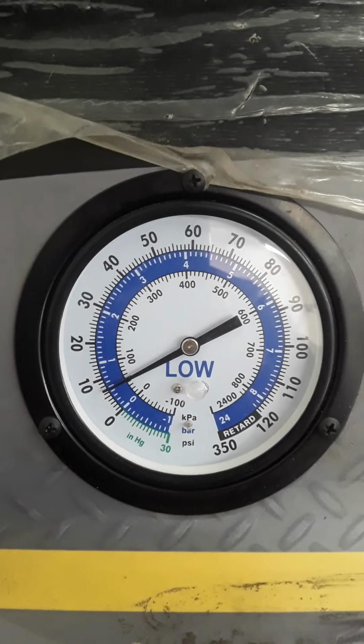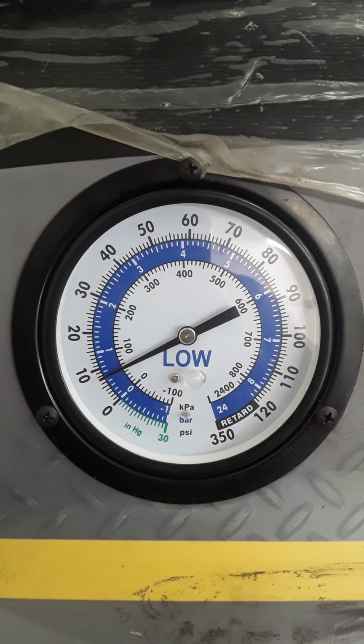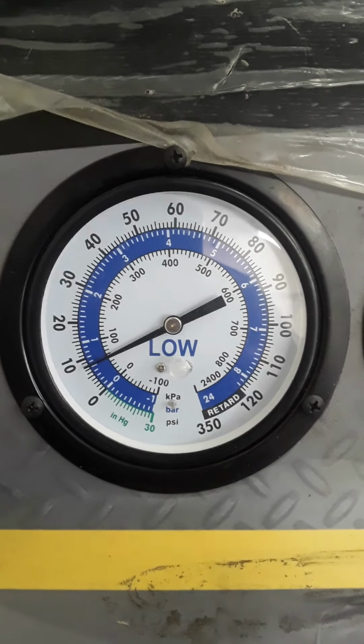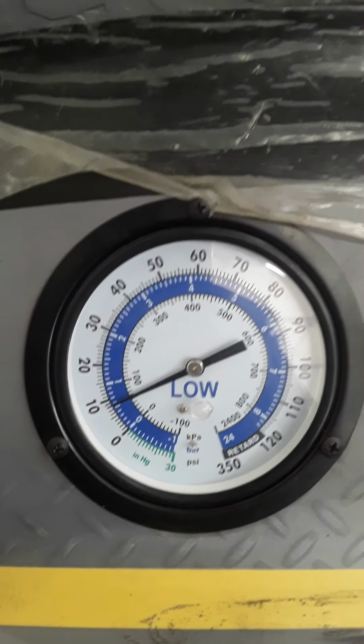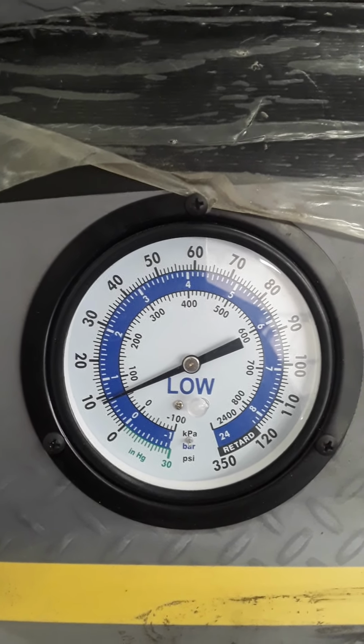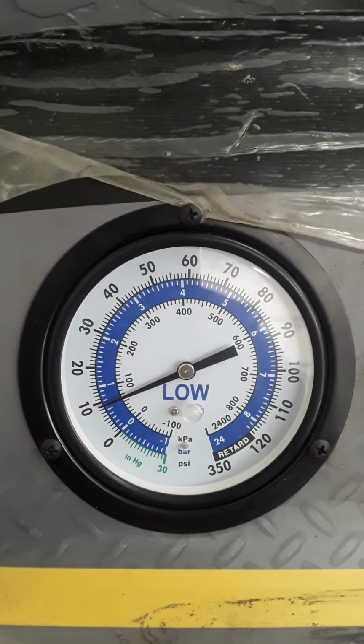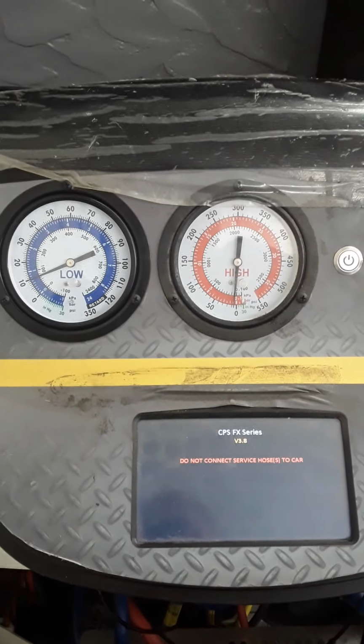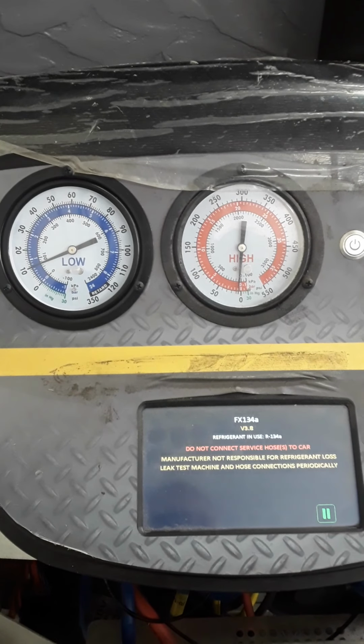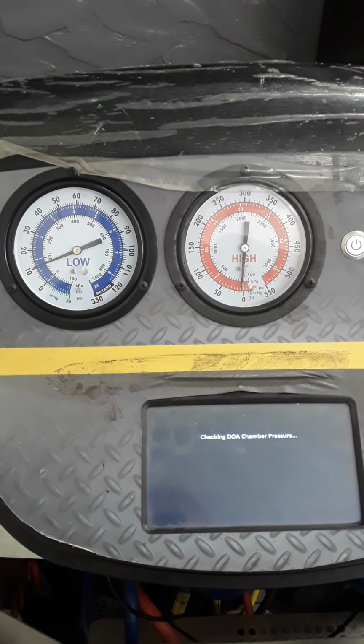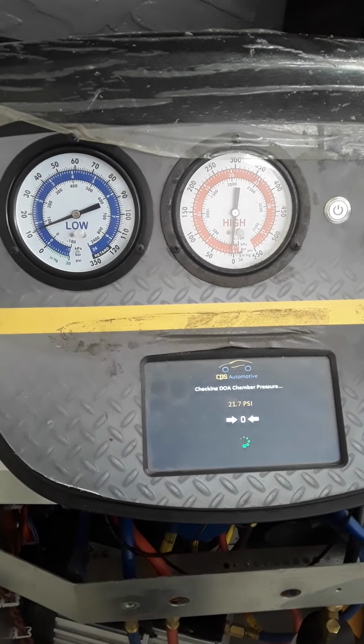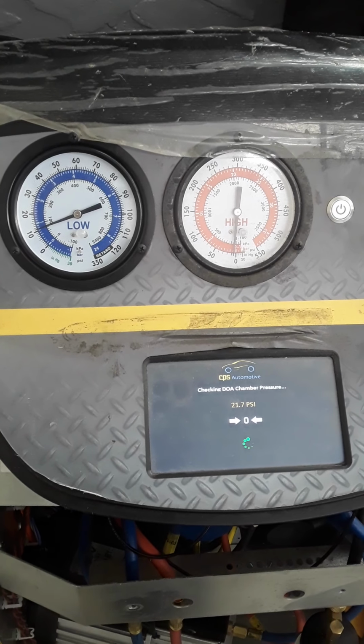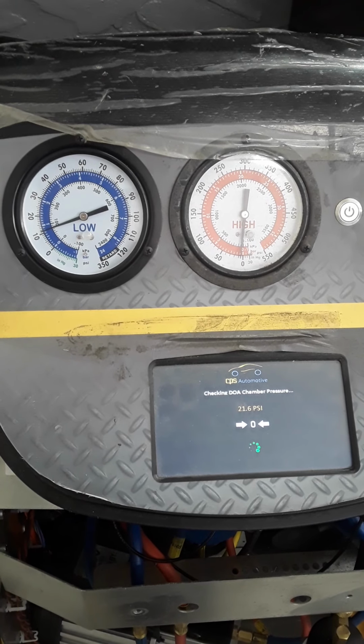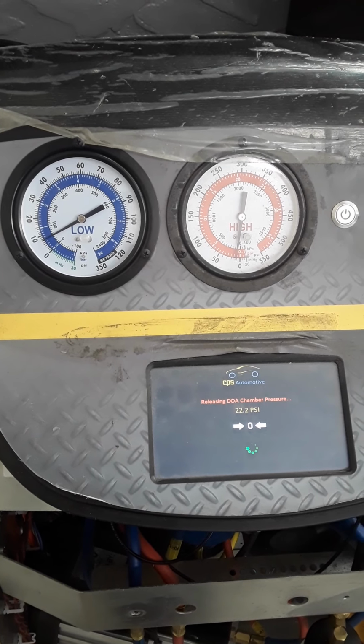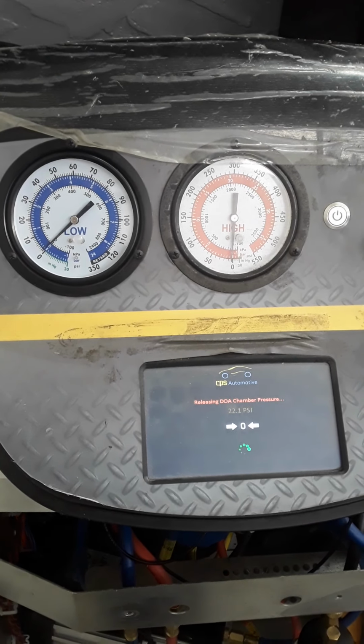I'm recording right now where that low side goes up. It goes up to about 10 pounds of pressure. Yeah, see, that was the thing I wanted to tackle: why is the pressure going back up? If the pressure is going up in any way at this point, it would have to be the charge or the purge. Well, that, or here again, everything he's told me leads to the brass fitting. That's what it is.